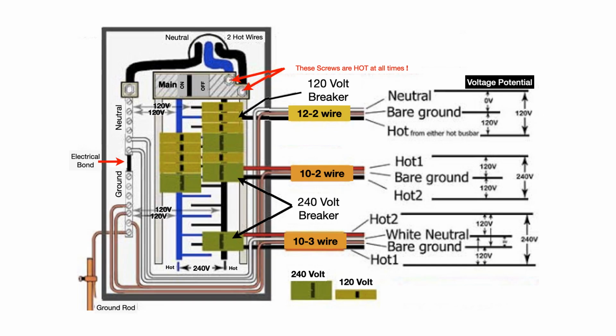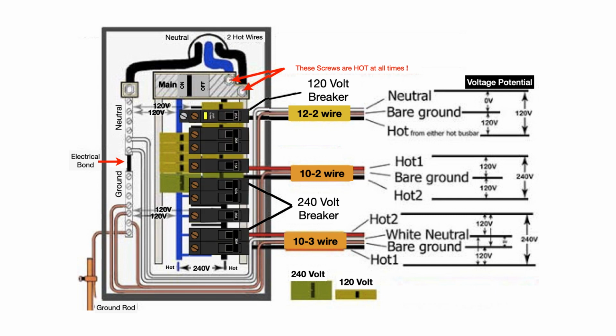We are now going to have a closer look at the connections inside a typical 200 amp service panel. The breakers are installed in a panel so that contact is made with one, or both, of the hot bus bars running down the middle of the box.